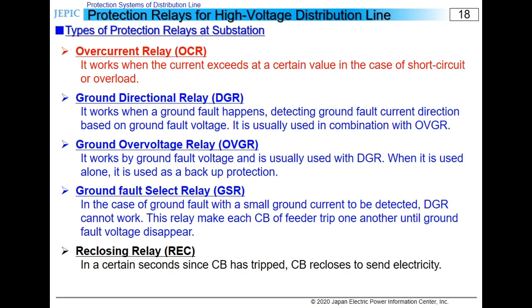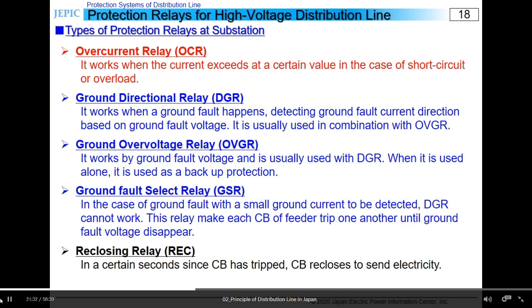Ground over voltage relay is also used as a backup protection. In the case that ground fault over voltage is detected but not ground fault current like a fine ground fault, being combined with ground fault select relay, each feeder is made to trip one by one until ground over voltage is not being detected. Reclosing relay is a relay to energize automatically feeder after CB is made to trip by either relay. Since there are some instantaneous faults like tree touching, this method is used. Furthermore, combination of re-energization and DAS detects the defected section.